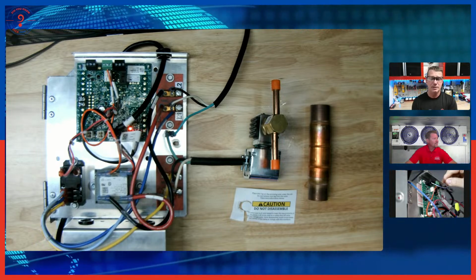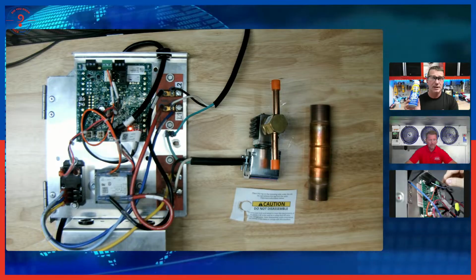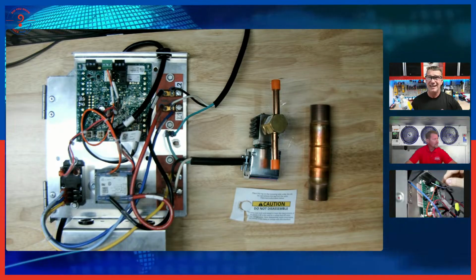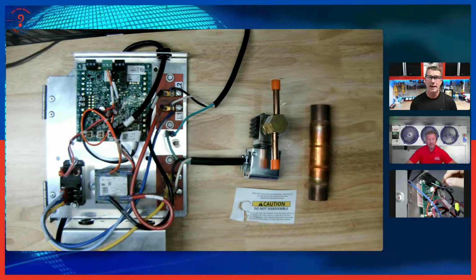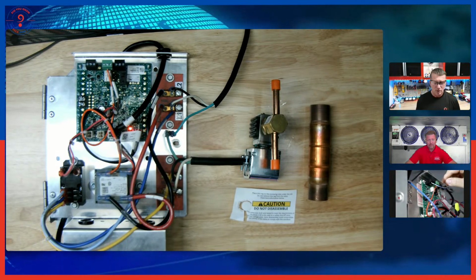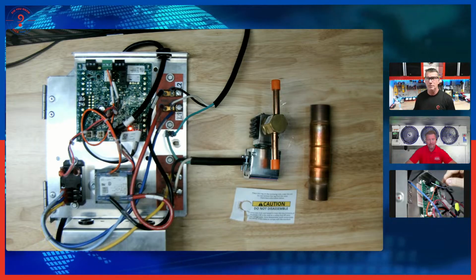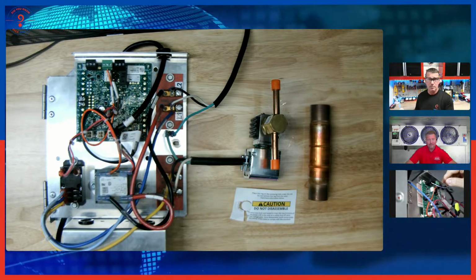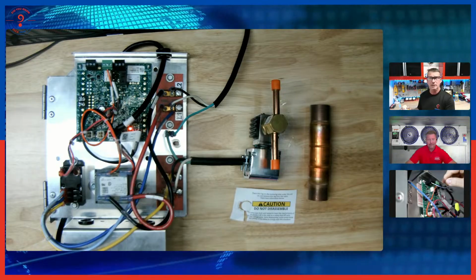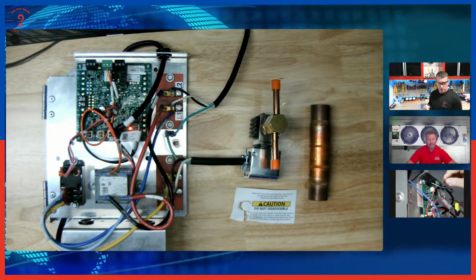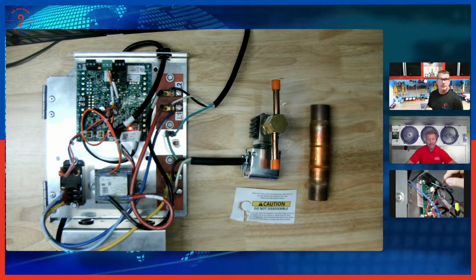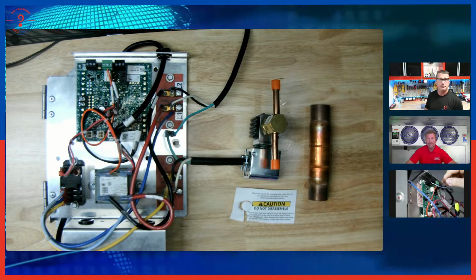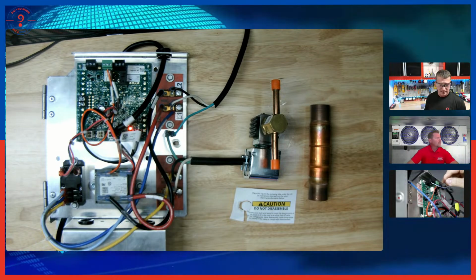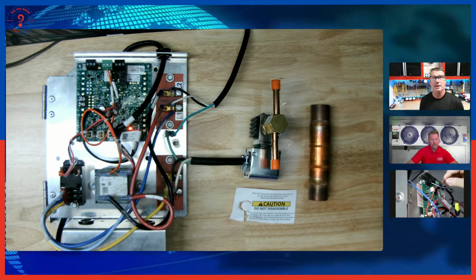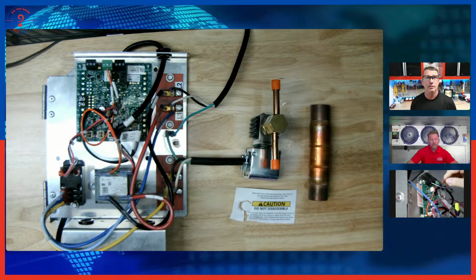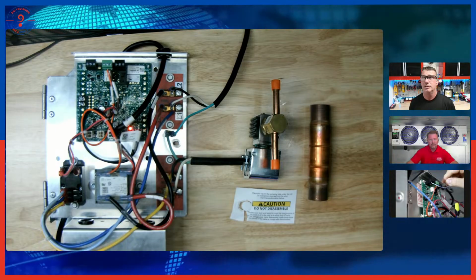So for test purposes, we're able to use this A2L refrigerant to get an idea of the sequence of operation on our controls. So we can actually do a test function of that. So we'll experiment. I don't have a good way of measuring my parts per million to be able to get down into that lower flammability level. So we'll do a small one and see if we get any detection off from it. I'll be very gentle with it and see, because it's going to be sampling. Most of them sample every 5 seconds or so, and they're going to be looking for amounts of refrigerant.